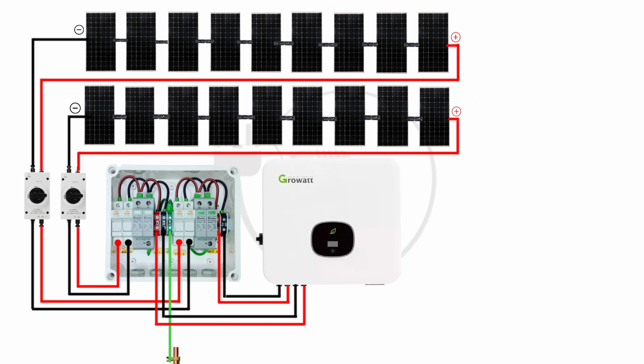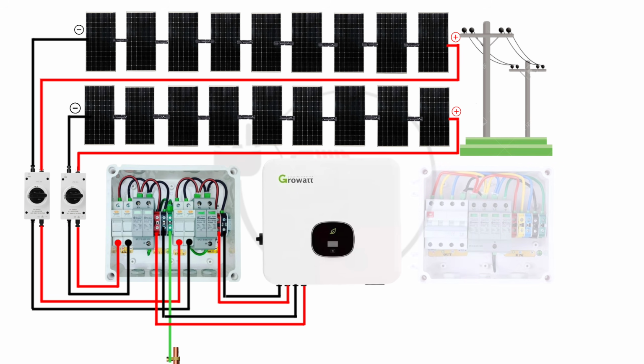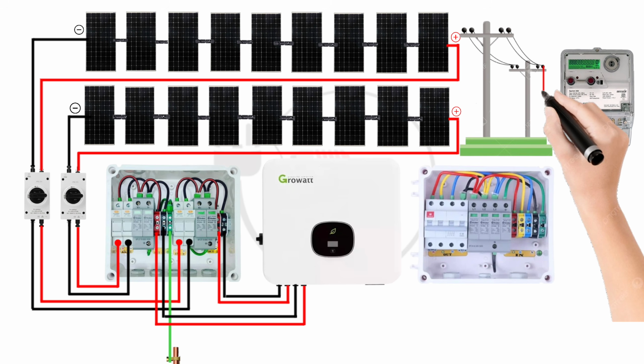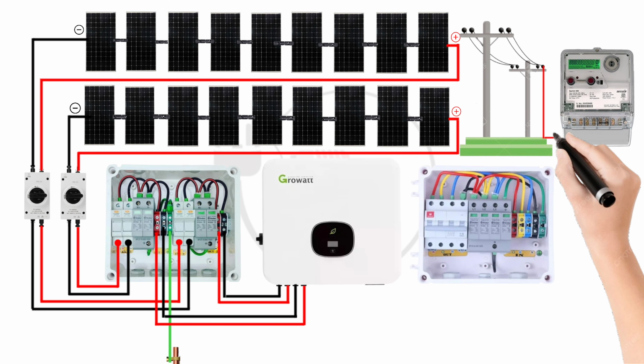How to connect a 10 kW AC side grid tie solar system. Now I will cover the wiring from the 3-phase grid supply to your inverter. Let's take a look at the overall wiring diagram. We will be connecting our 3-phase grid supply to the energy meter, then to a disconnect switch, SPD, MCB, and finally to the inverter. First we connect the 3 phases, RYB, L1, L2, L3, and a neutral from the grid.